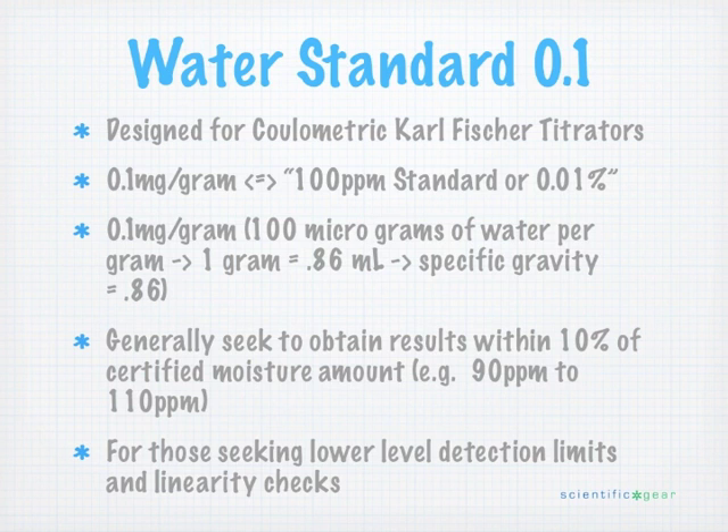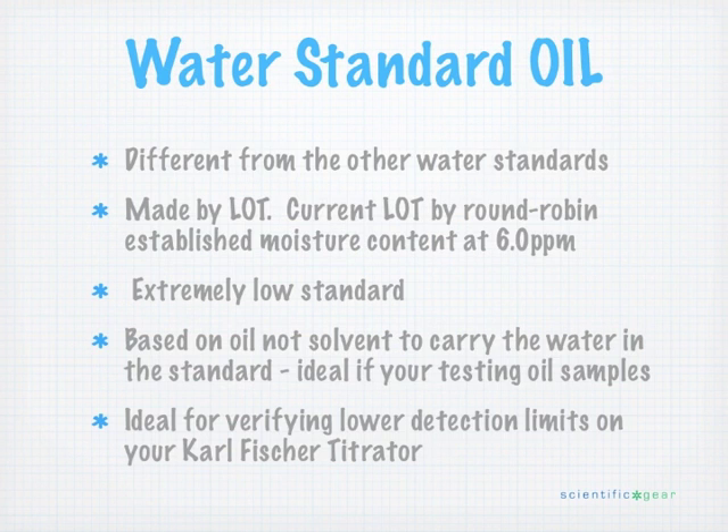The Water Standard 0.1 is a little bit more sensitive to moisture than the Water Standard 1, so whether you use it on a daily basis depends on your skill level. Last but not least, on the coulometric side, we have our Water Standard Oil. With this standard, instead of targeting an exact water content like the two previous coulometric standards, we analyze the material and release it at whatever water content it comes in at. Our current lot has a water content of six parts per million — extremely low. It is based on an oil as opposed to a solvent system, so you need a setup designed for analyzing an oil sample to use it effectively.